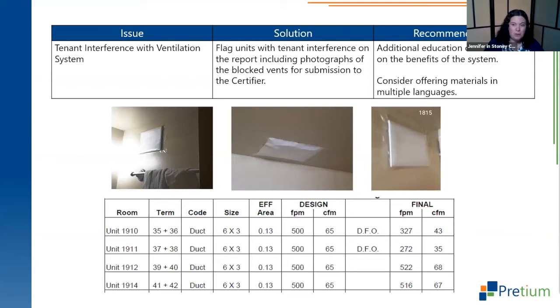So it puts us in a bit of a pickle. We're trying to get this balancing complete for an entire run of floors on an entire wing that's serviced by one mechanical unit. And essentially we can go in the unit one minute and 15 minutes later, it's covered up again. So what we ended up doing was speaking with the certifier about this. What we agreed upon at this point in time was flagging the units where we're having tenant interference on the reports and including photographs of the blocked vents for submission to the certifier, to identify the locations where this has been a problem.